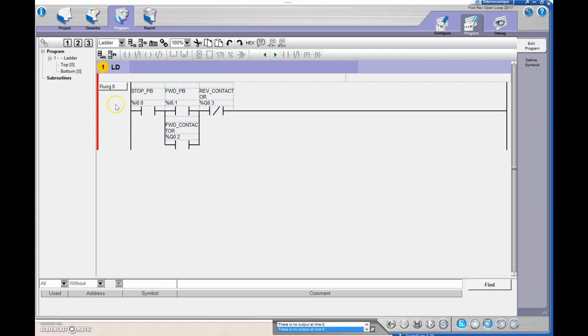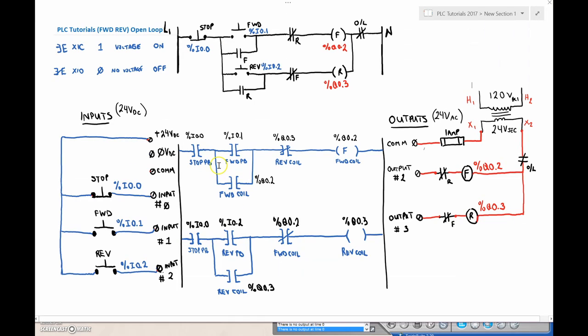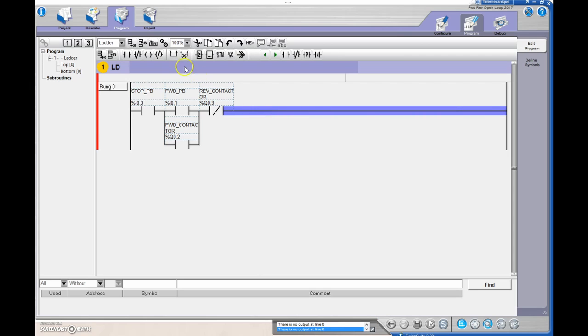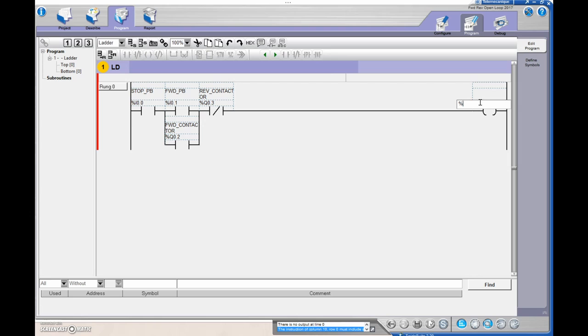We've got three instructions — same as this rung here — and the forward coil in parallel. The last thing in the rung is the output, and the forward coil is %Q0.2. So highlighting the rung and putting in the output, %Q0.2, that comes up as my forward contactor. That's everything we need for the forward contactor.